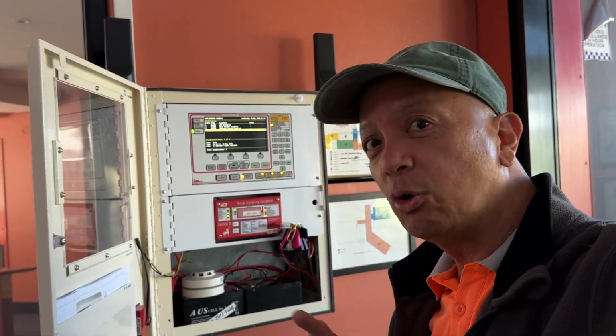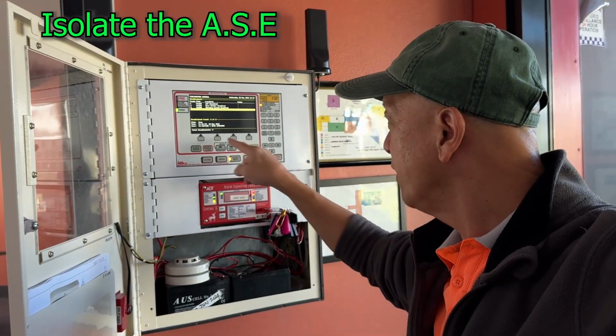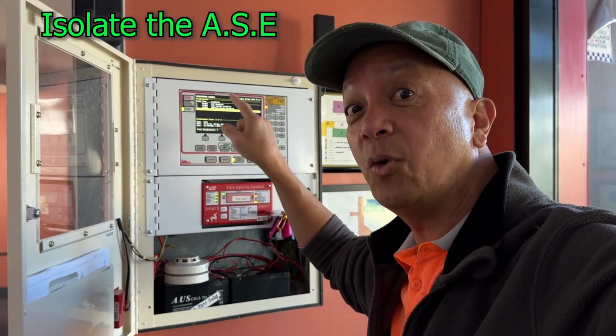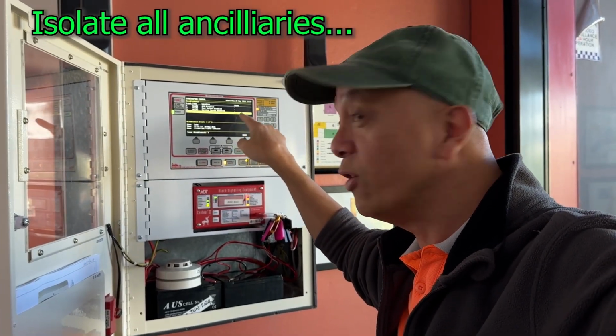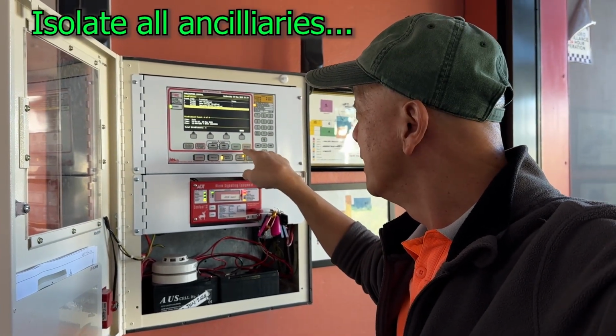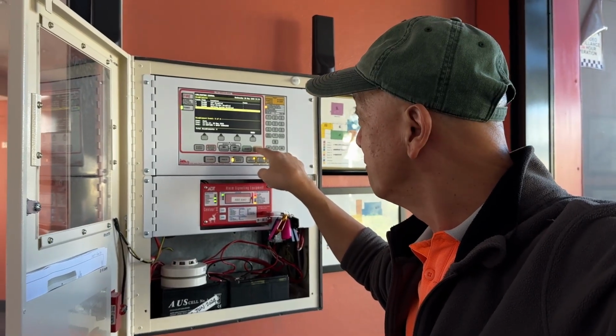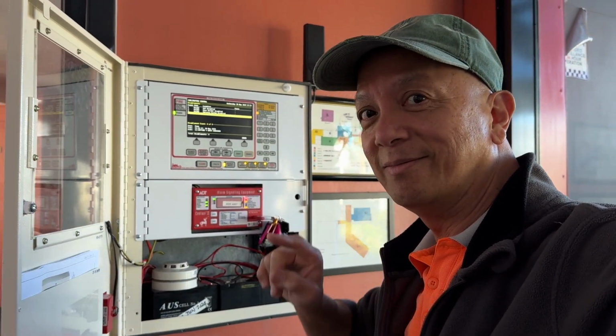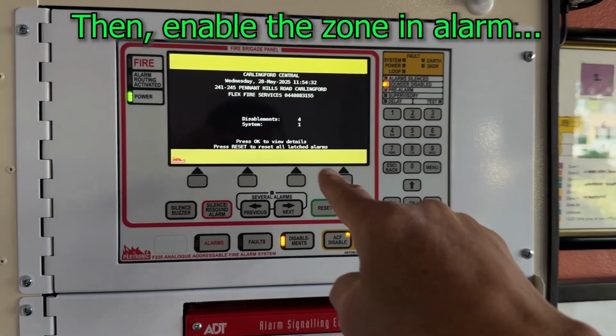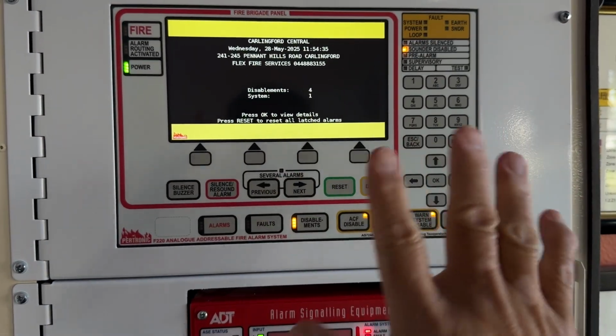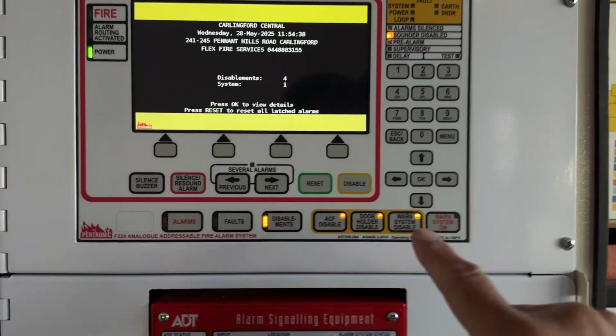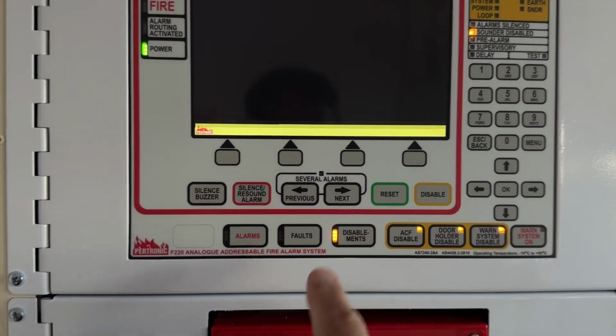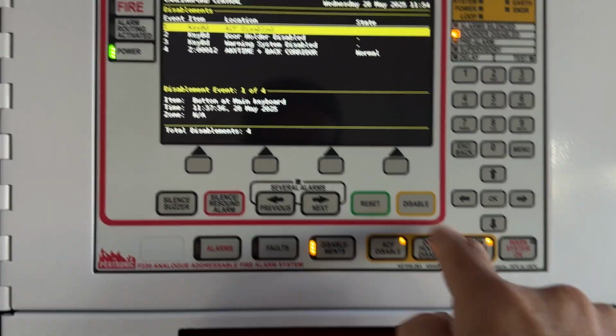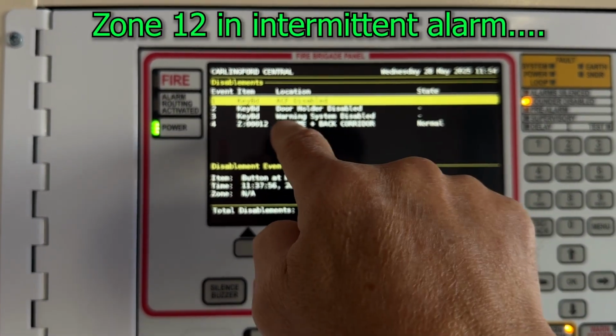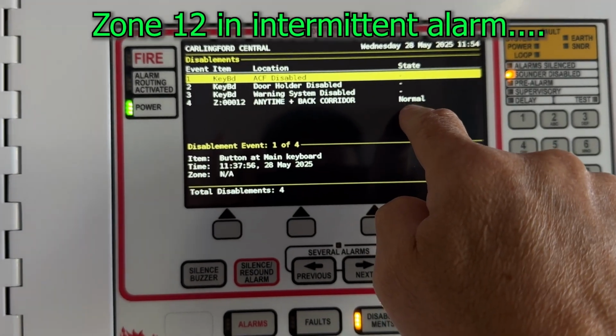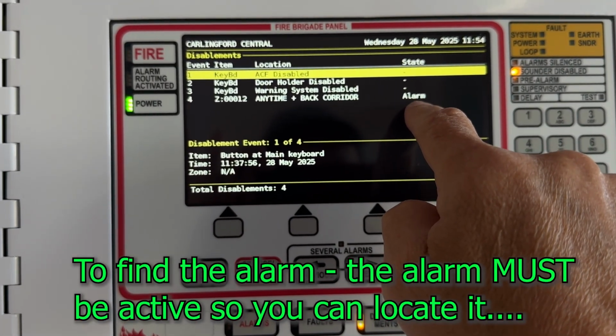So what you're going to do first is isolate the ASE, and then that particular zone in alarm. Before it's isolated, it now says back on alarm. What you're going to do is enable that particular zone, and let's do it. So this is the normal screen when you arrive on site. There's no alarm whatsoever. So you check for the disablement. This 1, 2, 3 is already disabled. Now that one, zone 2, is normal right now. And then back on alarm, look.